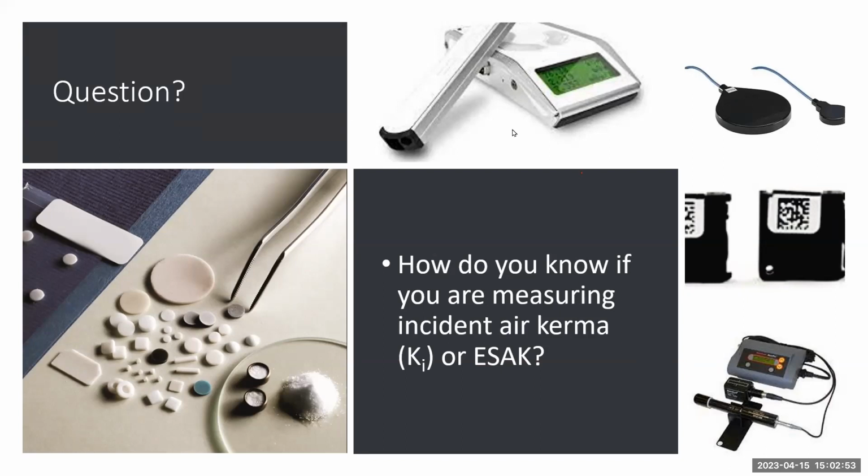If you are using this type of solid state detector where they have a lead back, that means the backscatter is blocked and not able to reach the sensitive volume of the detector. So even though you put this detector on, say, the phantom, you are measuring the incident air kerma.